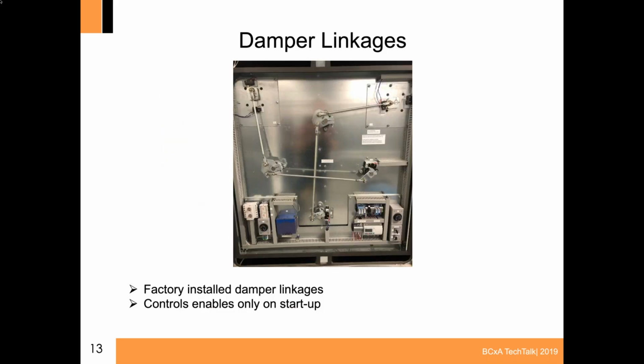So there are damper linkages that are factory installed that the controls contractor has absolutely no control over. They give the air handling unit an enable signal, and when they give it that signal, the 60-second cycles begin. The recirculation mode, unfortunately, is not programmed into this yet. It was not part of the approved sequences, but it is a recommendation to help out. The little black dials that you see in the bottom left and right-hand corners can help adjust that 60-second cycle to optimize the system, but it's factory set at 60 seconds, and that's what we were stuck with, I guess, with the installation.